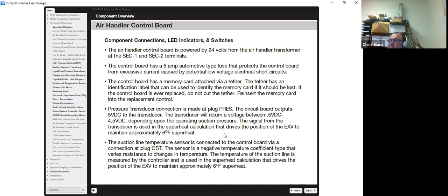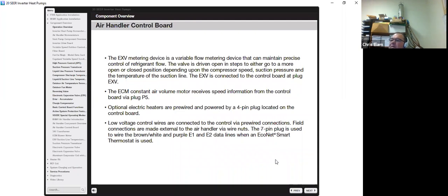You have a suction line thermistor, which is connected to the control board via plug OST. The sensor is a negative coefficient, 10k ohm resistor. The temperature of the suction line is measured by the controller and used to help calculate the superheat. The EXV metering device is a variable flow metering device that can maintain precise control of refrigerant flow. The valve is driven open in steps to go to a more open or more closed position depending on the control compressor speed. Suction pressure and temperature of the suction line will guide that. The EXV is connected to the control board at the plug EXV.